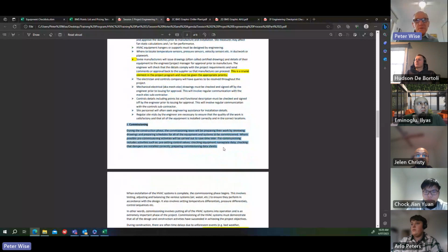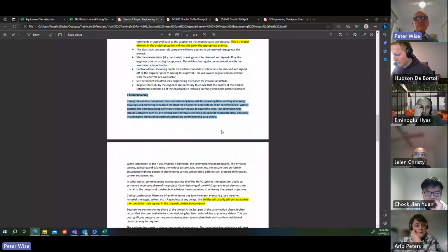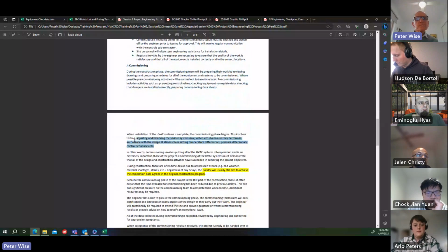So if you've got stat valves, you can preset those if you've done the calculations to work out what the pressure drop is expected to be. And that'll save time when they start balancing the water. Checking the equipment. So this is another check to make sure it's in the right place. They'll be looking at the equipment schedules and checking the equipment nameplate data and making sure that that is the right unit, and also putting that on their sheets. They'll be looking at dampers to make sure they're installed correctly and in the right places, and start preparing their sheets, the record sheets.